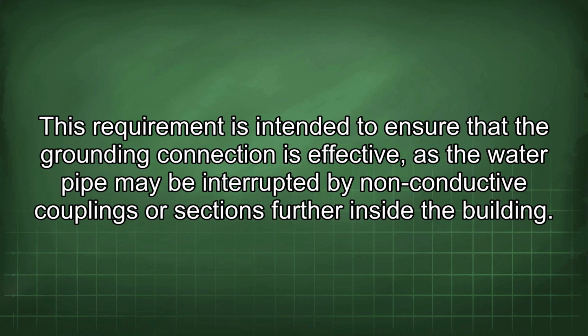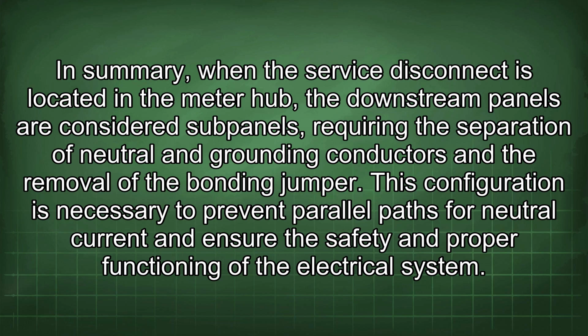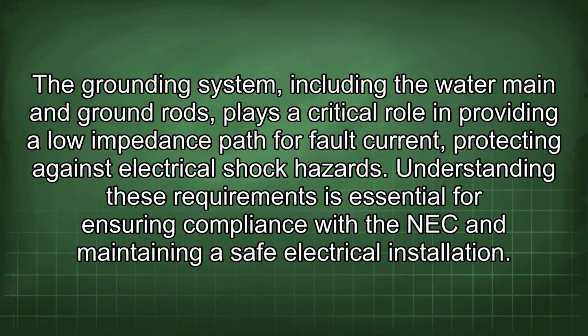This requirement is intended to ensure that the grounding connection is effective, as the water pipe may be interrupted by non-conductive couplings or sections further inside the building. In summary, when the service disconnect is located in the meter hub, the downstream panels are considered subpanels, requiring the separation of neutral and grounding conductors and the removal of the bonding jumper. This configuration is necessary to prevent parallel paths for neutral current and ensure the safety and proper functioning of the electrical system. The grounding system, including the water main and ground rods, plays a critical role in providing a low impedance path for fault current, protecting against electrical shock hazards.